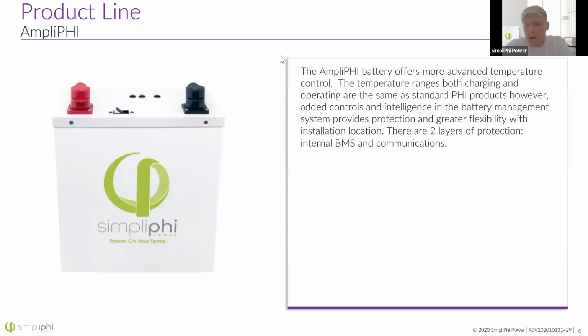Our AmpliPhi battery does offer much more advanced temperature control and protection, so this is a better option for those installing batteries outside in a cabinet or in a non-insulated shed in an environment that could get cold. Keep in mind, our Phi and AmpliPhi batteries are not outdoor rated. We are now offering a new ESS system that is outdoor rated and has much more functionality, especially as far as temperature goes. If you are installing a system outdoors, tune back in for our upcoming ESS training on our training calendar. However, today we're just going to talk about our standard product line, and note that these two batteries are not outdoor rated, so you'll need to protect them from rain, wind, and sun somehow.